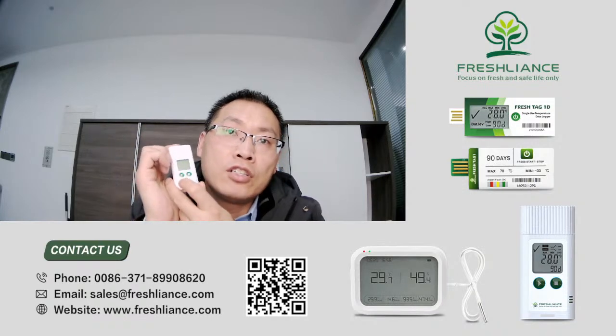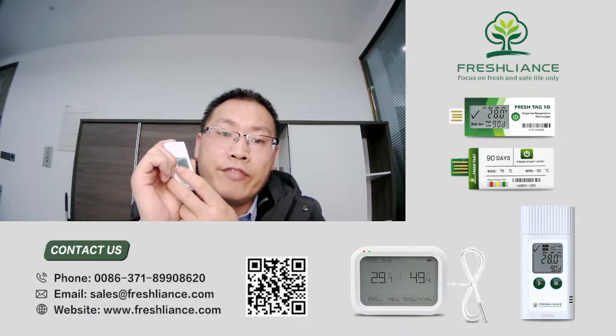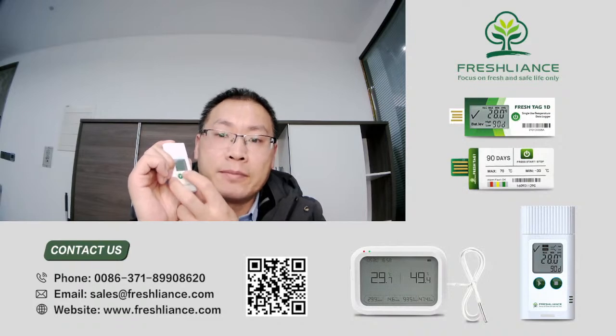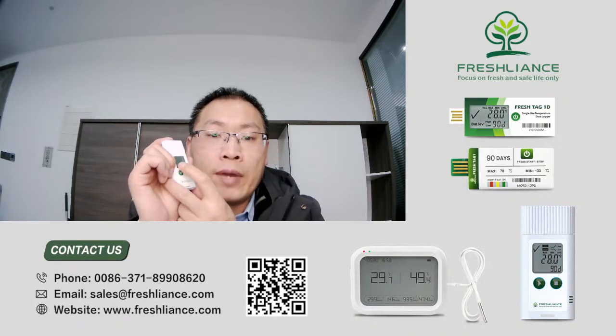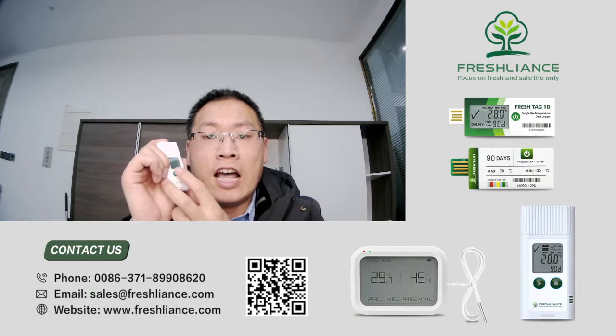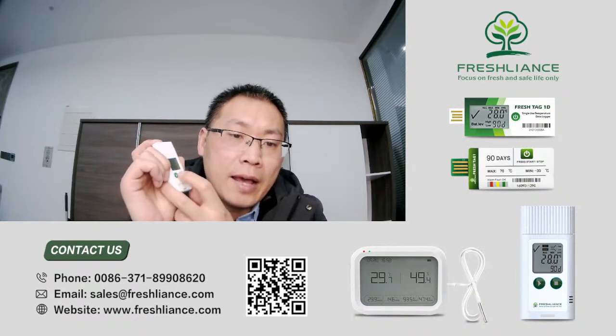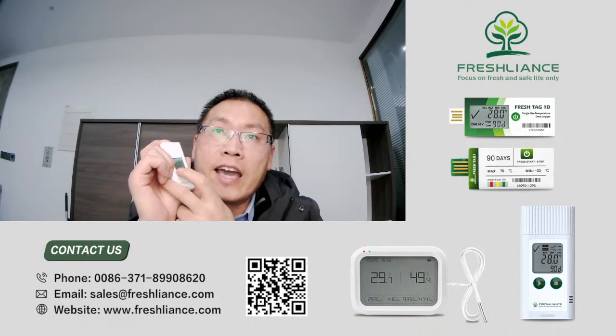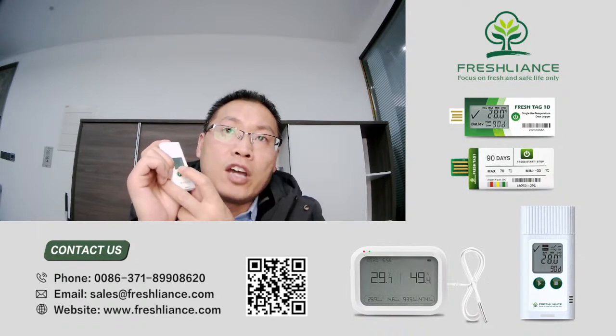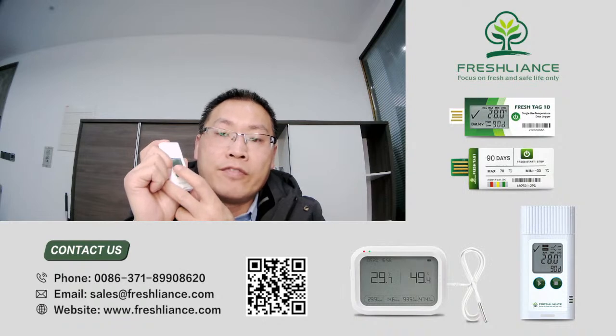Our Tech Plus data loggers have alarm functions. You can freely configure all the parameters through the configuration software provided by our company. Through our configuration software, you can set the alarm types, alarm delay, and the alarm threshold. Tech Plus T or TH will alarm when the temperature is higher or lower than the alarm range for some time. That will help you find the abnormal status and adjust it in time to prevent further losses.